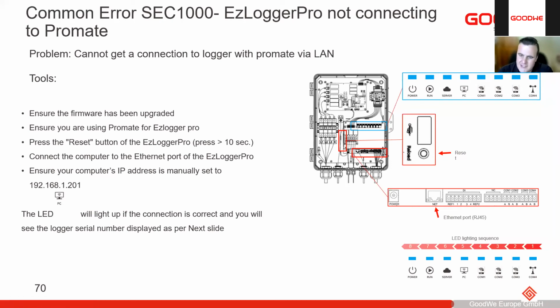You hold it for roughly 10 seconds, then you need to see the LEDs. These blue LEDs will cycle from right to left. When they cycle from right to left, we know it's been set to static IP. If they go from left to right, it's been set to dynamic. So we set that to static. We press and hold that for about 10 seconds, let go, and we should see that sequence. If we don't see the sequence, we need to try it again, maybe hold it for a little bit longer, and let go of that button, and then we should see that LED sequence running.